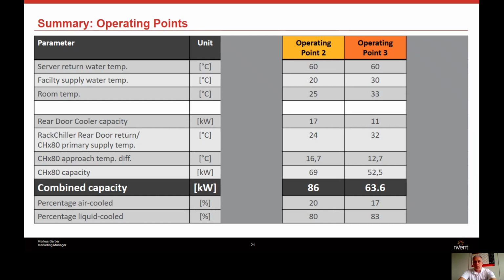When you now move up a little bit the chain to operating point 3, you will see, okay, what is happening if my supply water temperature is at 30 degrees? Of course, you have to accept the higher room temperature. The cooling performance of the rear door is going slightly down. So therefore, the overall performance of the combined system is going down to 63, which is still a lot. The percentage on air and liquid is still in the row, and you could say, okay, this is something I can consider.